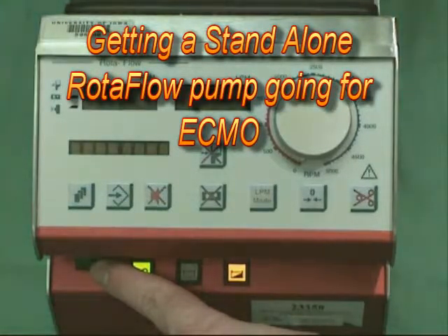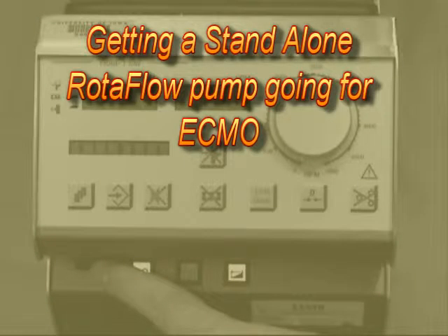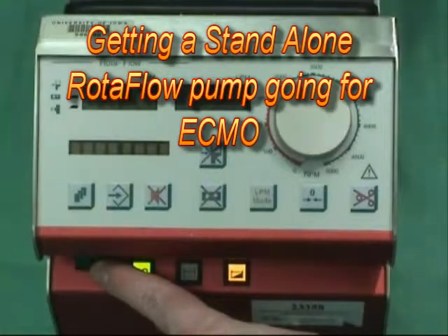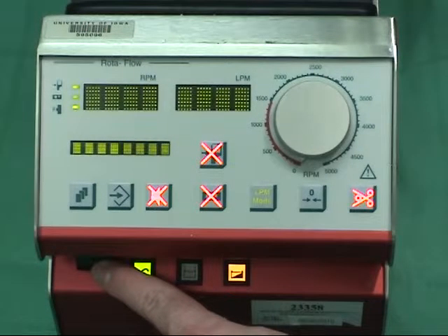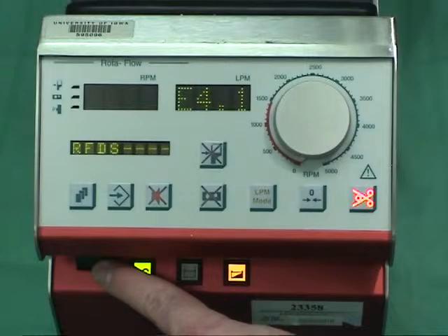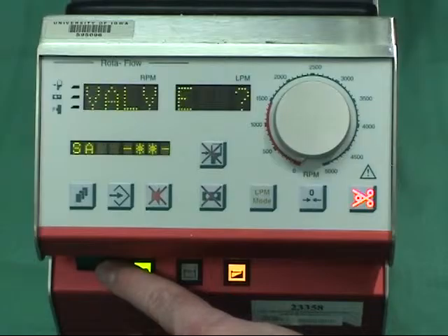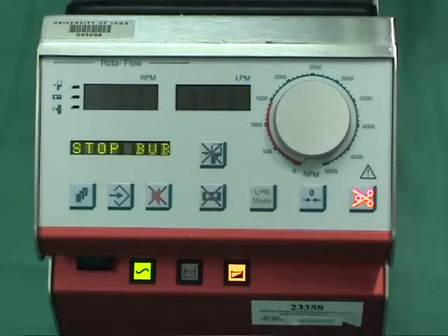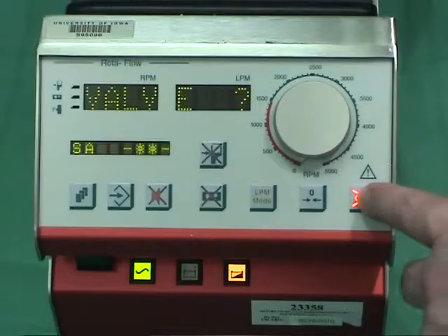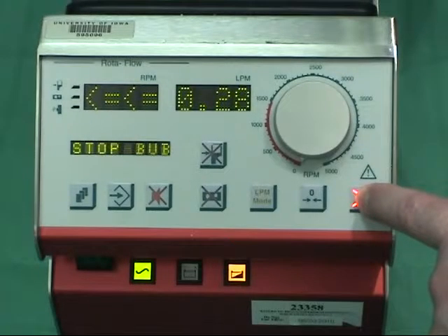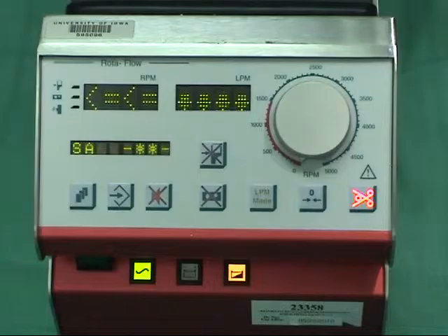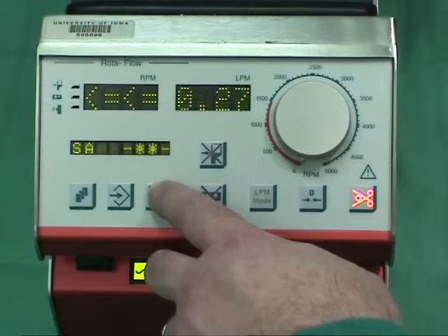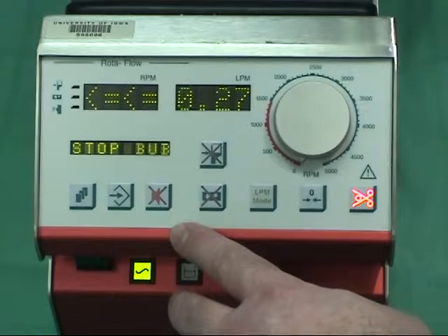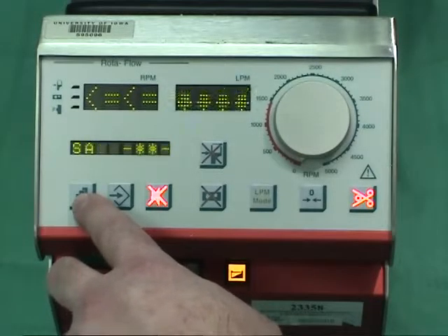So, how do we get a standalone RotaFlow pump going so as to initiate ECMO? Follow these steps and success will be yours. First, we need to turn on the console by pressing the green on-off switch. A self-test is initiated with an audible alarm. Valve appears in the LPM and RPM display. Ensure that a clamp is placed post-pump. Press the clamp button once and press alarm silence. Next, we need to set the pump in stand-alone mode.